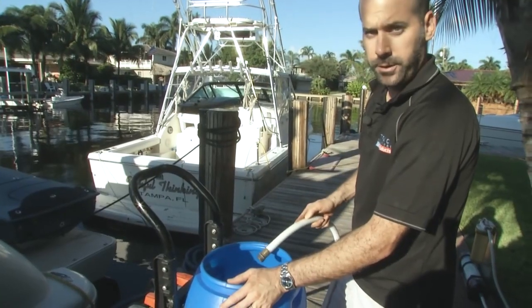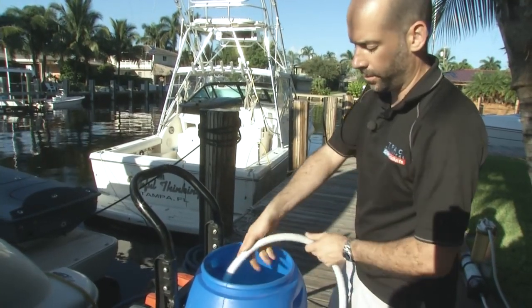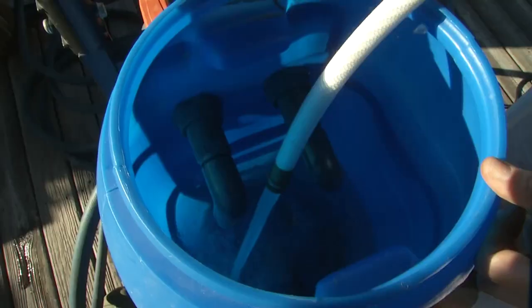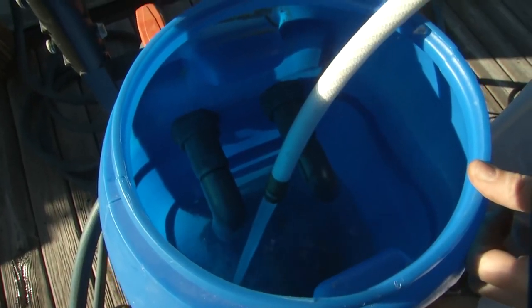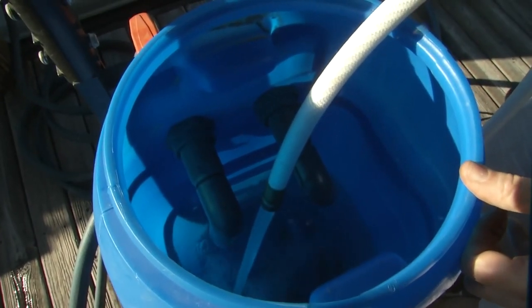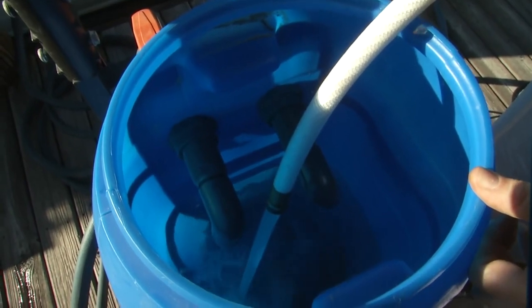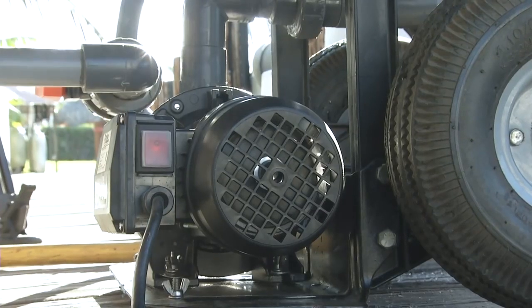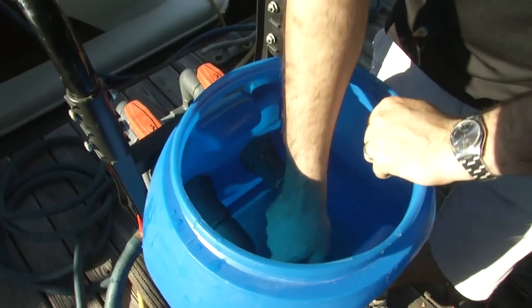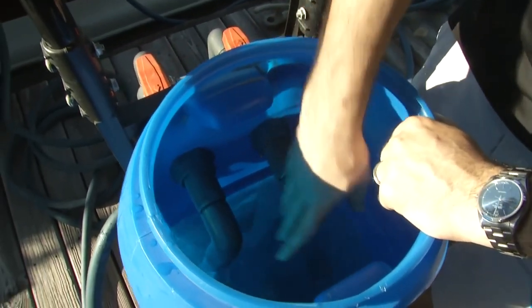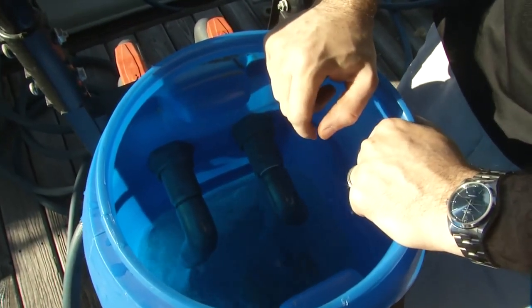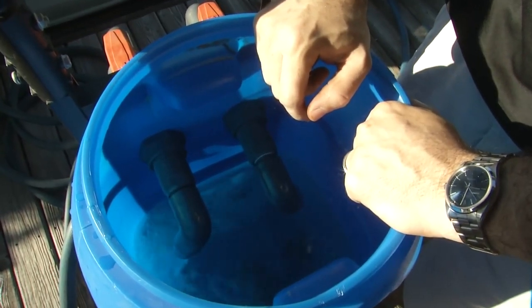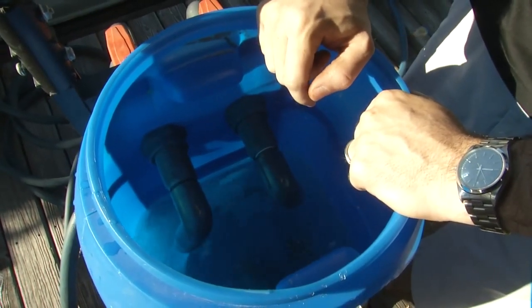Now we're ready to start filling the system. We're going to start by filling the bucket with fresh water. Once we have the suction fully covered, we can go ahead and turn the pump on. You can see here now we're getting a return from our system. So now we're just going to let it run for a little bit to make sure we've evacuated all the air from the system.